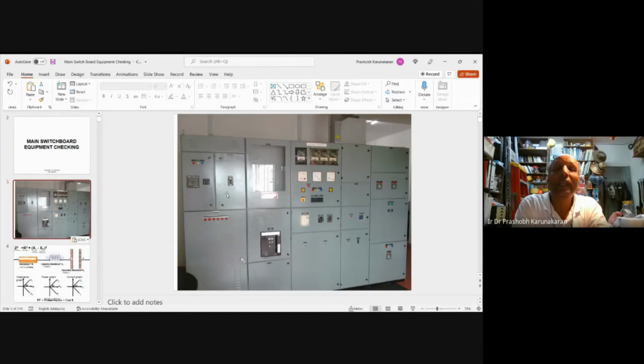They can kill you because they store charge, just like a battery. So every time you want to repair or change a capacitor, discharge it first. How do you discharge? At the bottom of this MSB, there is an earth bar - a 1 inch by 1/8 inch copper bar running the full length of the MSB at the bottom. Use a crocodile clip, clip onto that, and then put it on the 3 terminals - you see the capacitor has 3 terminals.